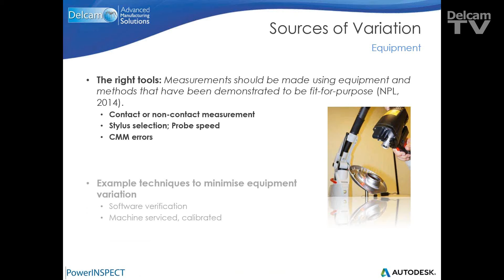So there are mechanical errors in the CMM, such as the perpendicularity, the parallelism, or the squareness. So, for example, you might have a linear axial variance whereby the y-axis is not exactly perpendicular to the x-axis, and you've got in many packages of software the ability to build a table of compensation values, and the video that you can see here for PowerINSPECT shows how exactly that works. So you've got a known artifact, and you know on that artifact that the machine should, for example, report a value of 10, just to make things very simple. Instead, you can see that your machine might be reporting the value of 9.99875, for example. Now that variance between the 10 and the 9.99875 is the linear axial error.